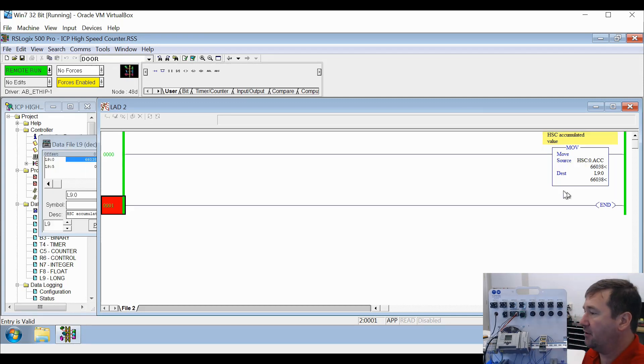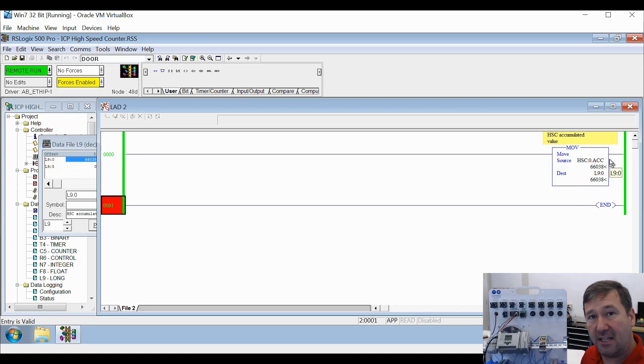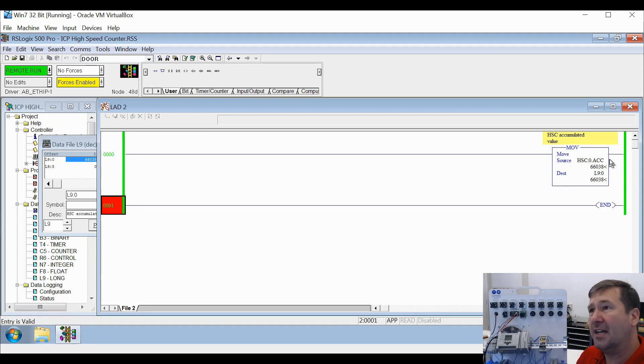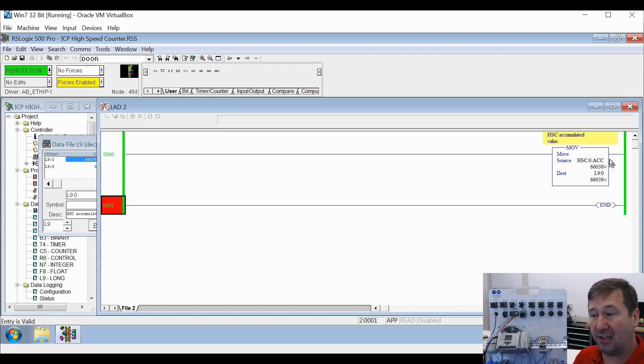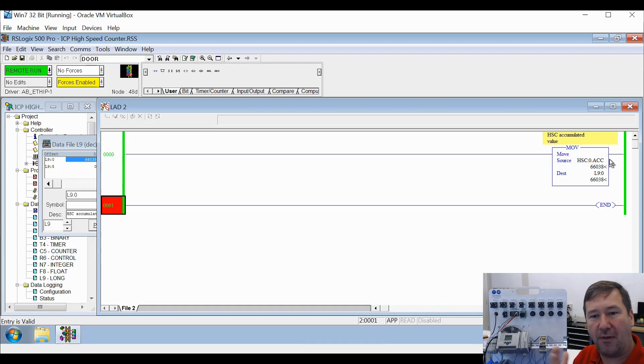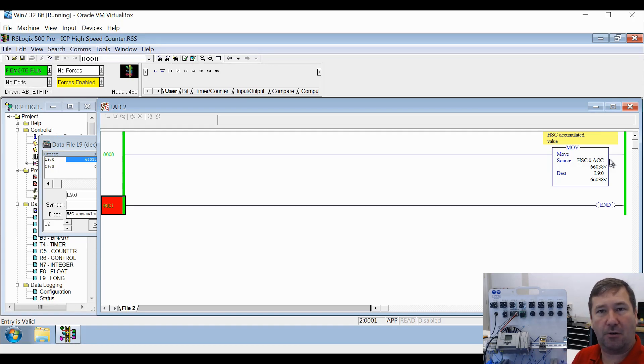What we're going to do is add some rungs to monitor this accumulated value and see if it's changing. I'm going to put a timer in first because I want to make sure that it has to say it stopped for a second before we say that it has stopped. This will be very useful in applications where a machine has a little vibration, so that whatever you're doing is not going on, off, on, off all the time.